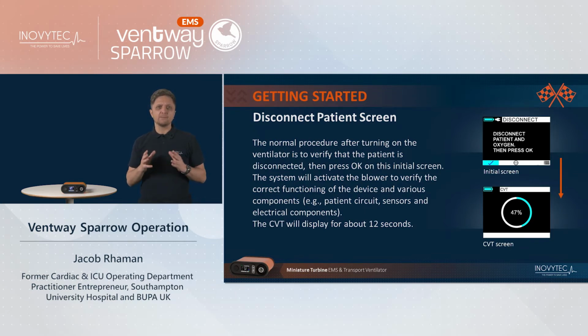Connect the patient circuit to the ventilator, ensuring that the flow sensors are connected securely. This can only be done in one way. Remove the blue stopper from the patient end of the circuit and press tick using the knob on the user interface. The system will activate the blower and verify the device functions and components to make sure that they are working properly. This includes the patient circuit, the sensors and electrical components.